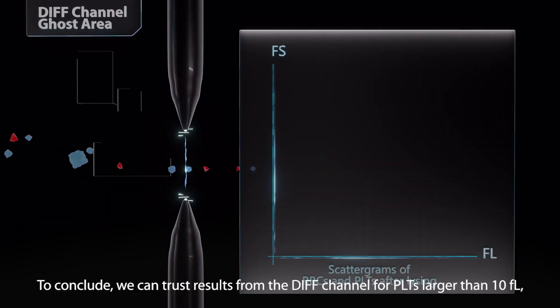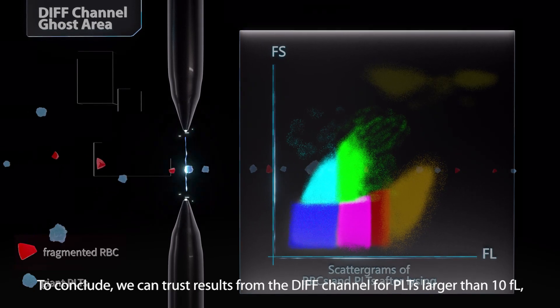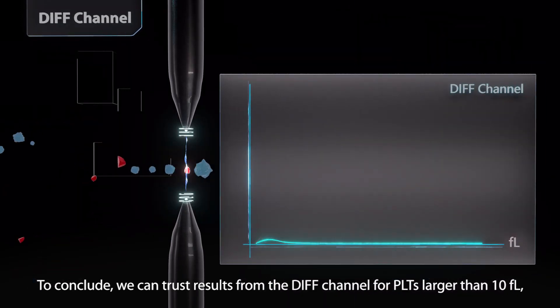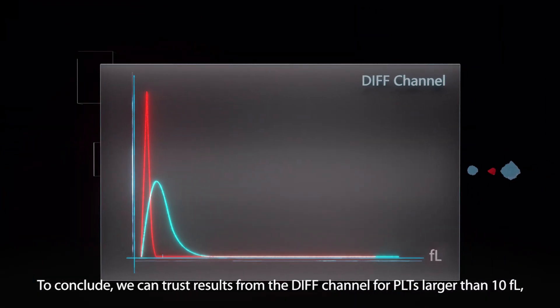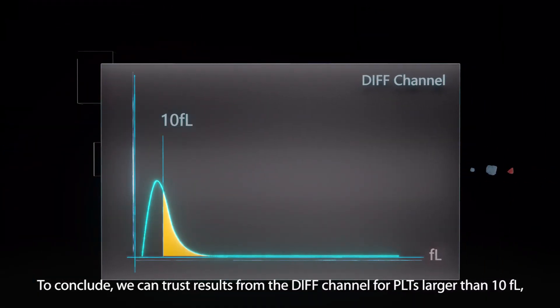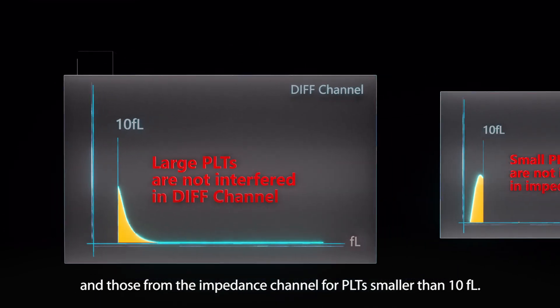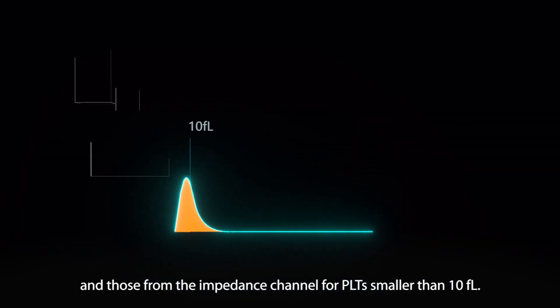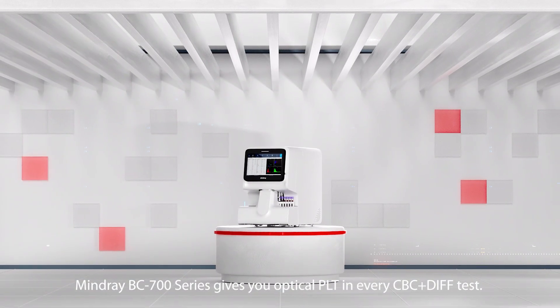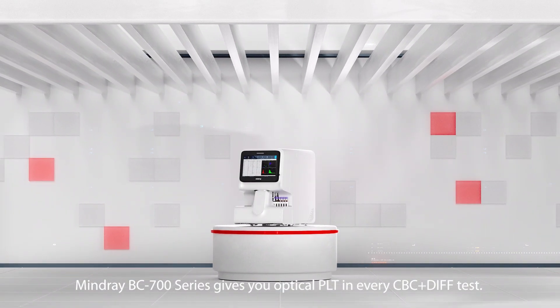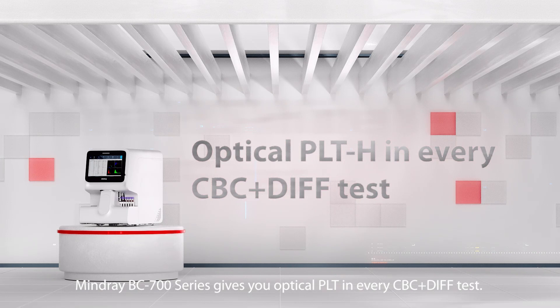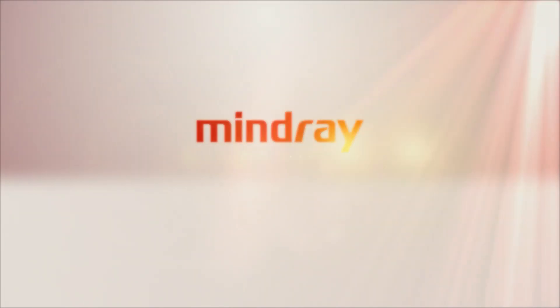To conclude, we can trust results from the diff channel for PLTs larger than 10 femtoliter, and those from the impedance channel for PLTs smaller than 10 femtoliter. MINDRAY BC700 series gives you optical PLT in every CBC plus diff test.